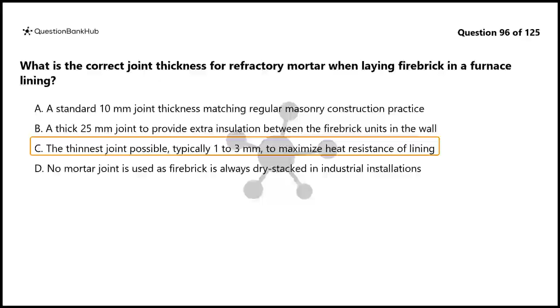The correct answer is C. The thinnest joint possible, typically 1 to 3 mm, to maximize heat resistance of lining. Refractory mortar joints should be the thinnest possible, typically 1 to 3 mm, sometimes described as a dip joint or wipe joint. Thin joints minimize the amount of mortar in the lining because mortar is generally weaker than the firebrick at high temperatures and is the first point of failure.